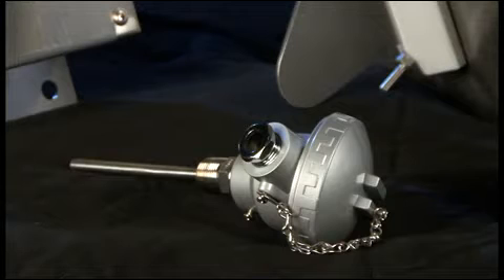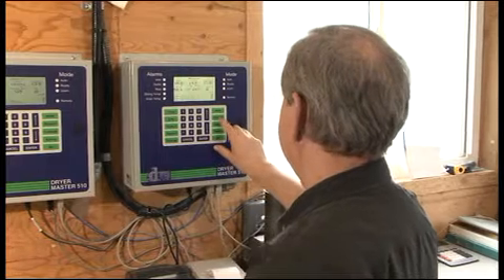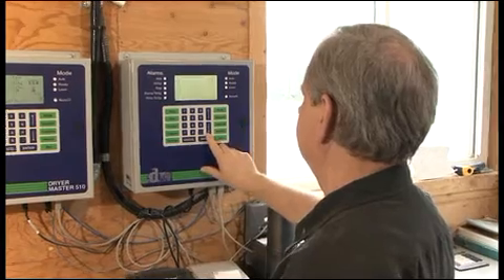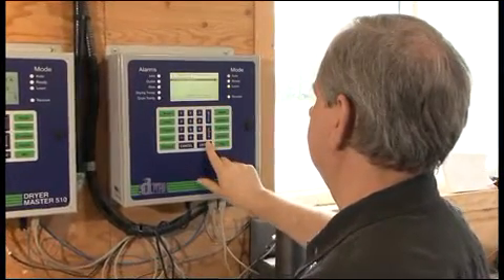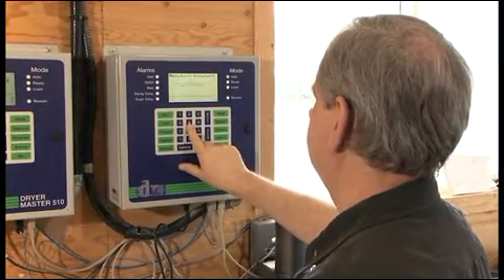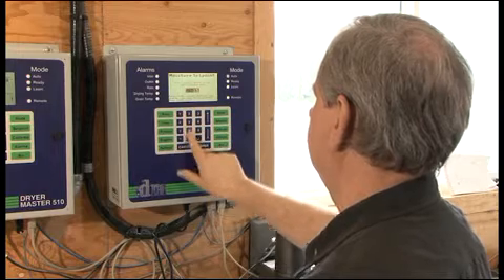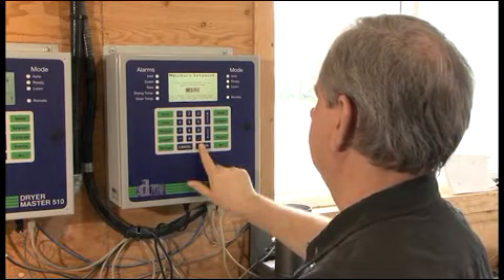An air temperature sensor is placed in the dryer to measure the drying air temperature. The moisture sensors, sampling button, and air temperature sensor are all wired to the Dryer Master 510 panel, which becomes the new workstation for the operator to monitor and control the dryer.